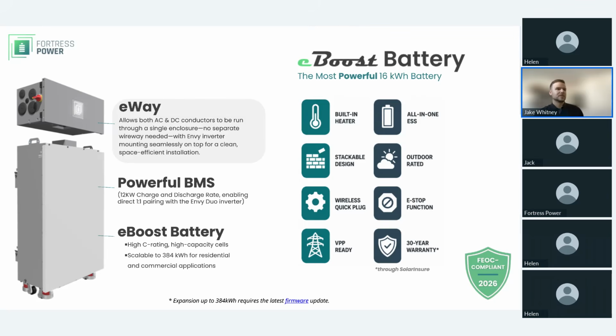The eBoost does have some unique features, one of which is that it's both indoor and outdoor rated, which allows flexibility of install. There's a built-in heater inside the battery that kicks on at 30 degrees Fahrenheit inside the battery cabinet, not exterior temperature, and it can go as low as -4 degrees Fahrenheit. It can still operate lower, but cold temperatures do affect the charge and discharge capacity of any battery.